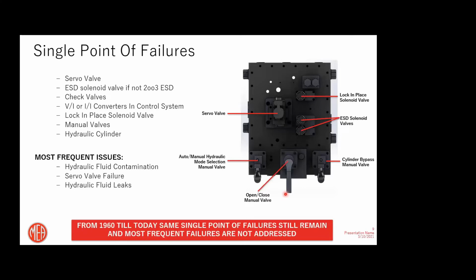are the servo valve, ESD solenoid valves if it's not 2 out of 3 ESD, check valves at 1 out of 1, V to I or I to I converters in a control system, lock-in-place solenoids, manual valves, and the hydraulic cylinder. One of the main things is the servo valve and the ESD solenoid valves: the ESD solenoids were addressed with 2 out of 3 ESD, but the servo valve was never addressed. If you go back, this is one of the most common failures, which directly relates to fluid contamination. And of course, we never addressed hydraulic fluid leaks. So from 1960 till today, the single points of failure still remain, and the most frequent failures are not addressed.